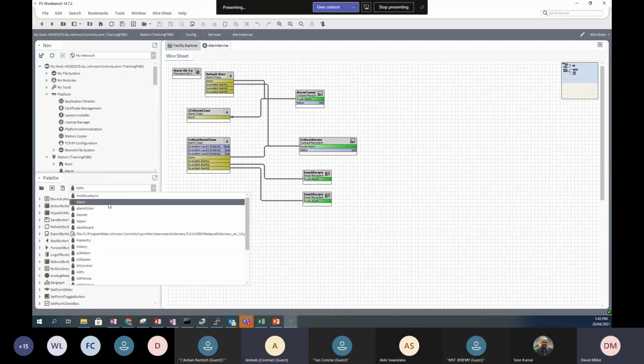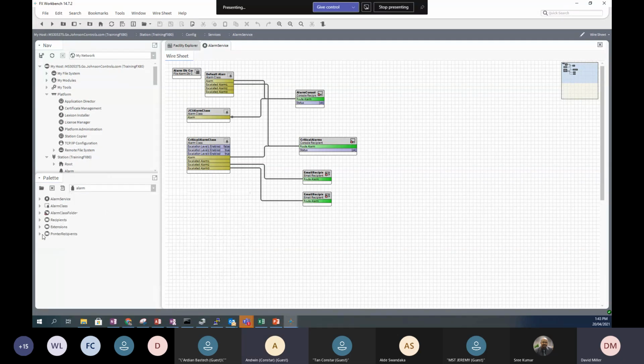So you have, so to show the arrangement that you have. Isn't this caused by too many alarms, so you will have some lagging or some miss out, because we have quite a number of alarms triggering at one time, maybe sometimes 10 alarms or 5 alarms per FX80, so it will make around 25 to 50 alarms at one time.